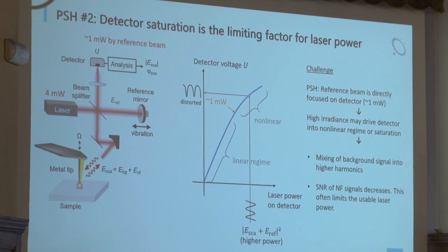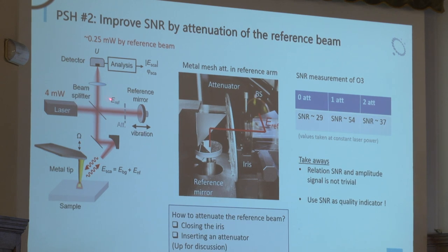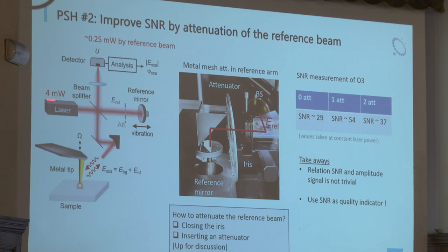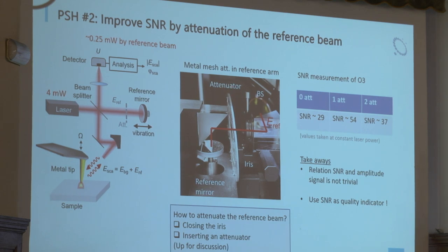In SNOM we are modulating the signal, so we have a DC power level from the reference arm and then our modulated signal on top. We want the intensity signal to translate linearly into voltage. If the reference beam is too intense and we are in the nonlinear region, the signal gets distorted — the background might modulate into higher harmonics and the noise level increases. The solution is to place an attenuator in the reference arm to reduce power to the detector. We use a metal mesh attenuator in our labs.